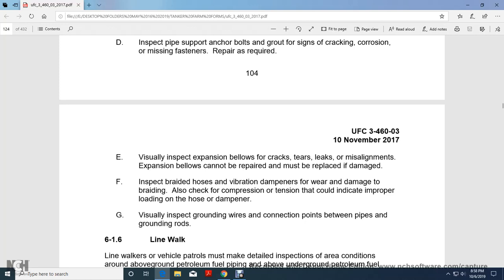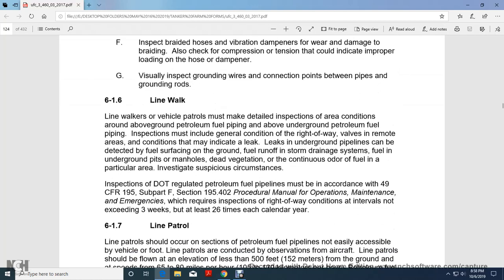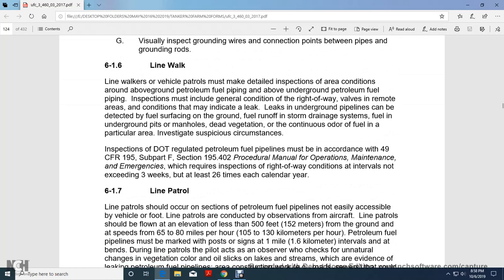Inspect braided hoses and vibration dampers for damage to the braiding, and also check for compression or tension that could indicate improper loading of the hose or damper. Visually inspect the ground wires and connecting points between the pipes and grounding rods. Line walkers or vehicle patrollers must perform a detailed inspection of the area conditions above ground petroleum fuel piping and above underground petroleum fuel piping.